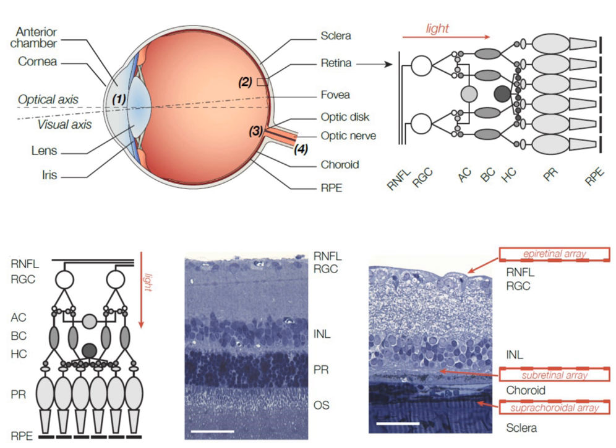The real-time image processing involves reducing the resolution, enhancing contrast, detecting edges in the image, and converting it into a spatio-temporal pattern of stimulation delivered to the electrode array on the retina. The majority of electronics can be incorporated into the associated external components, allowing for a smaller implant and simpler upgrades without additional surgery. The external electronics provides full control over the image processing for each patient.